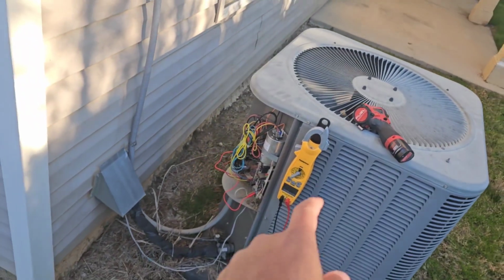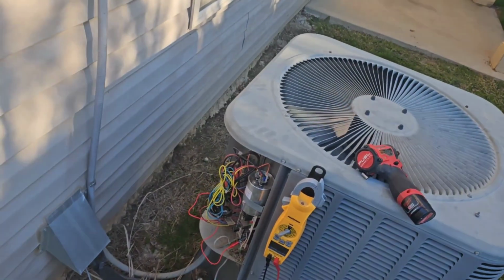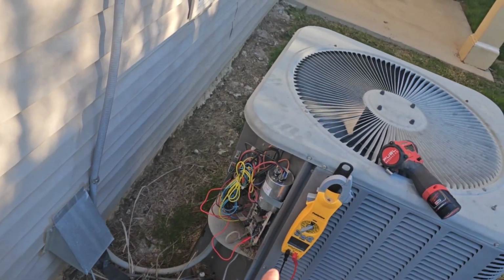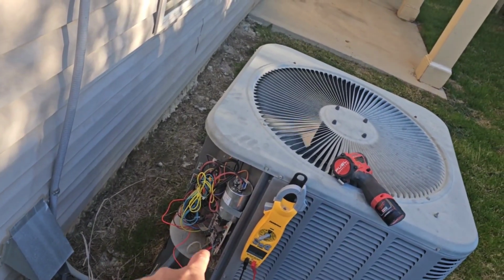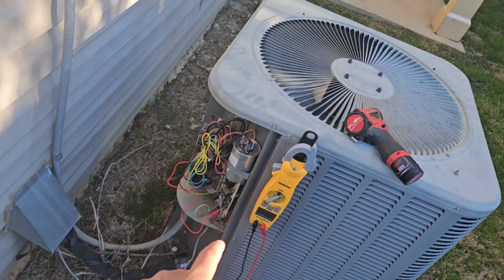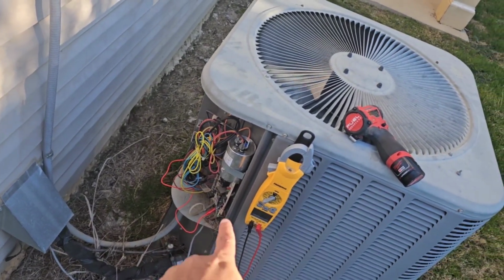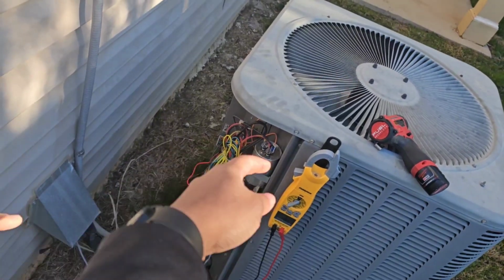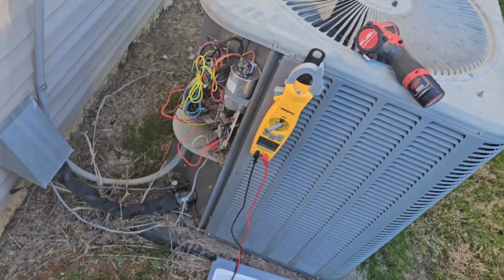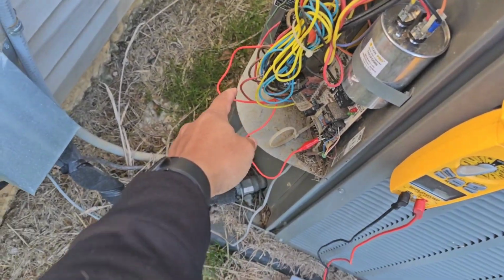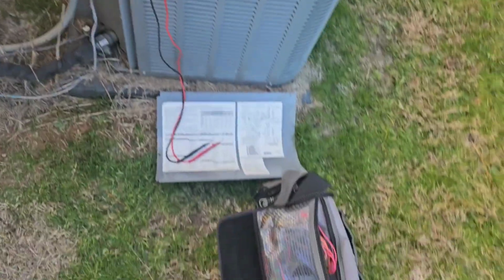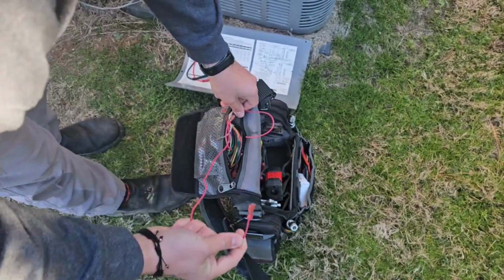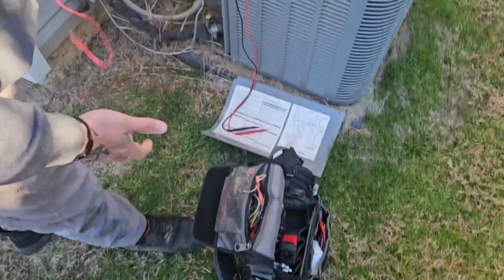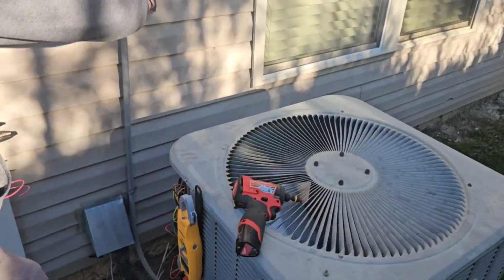So what you got to do now is bypass it right now so that we can get them going until we can get a new defrost board. Just take the jumper off completely and put a regular wire out of your bag, tie it into that yellow, put a crimp connect on, and put it on the contactor where you got the jumper at. Take one of these extra wires out, put a female crimp end. Yep, that one's fine right there. And you'll strip one end, put it on the Y1 spot, pull the disconnect too so you don't, yeah.